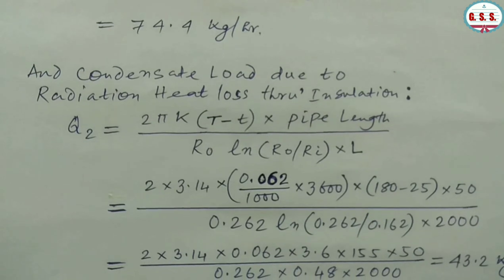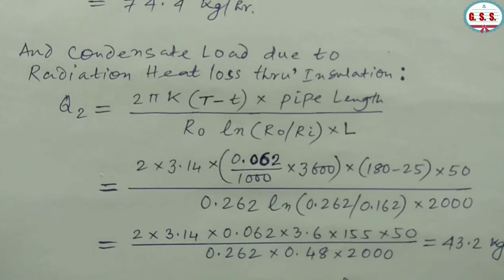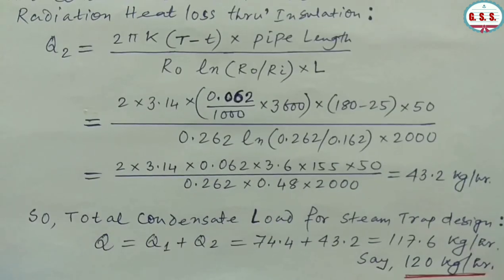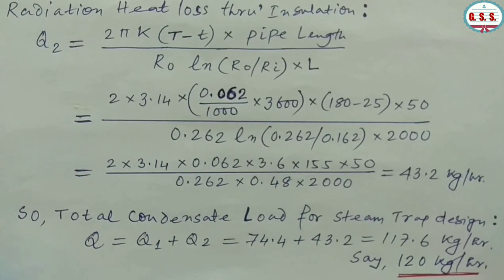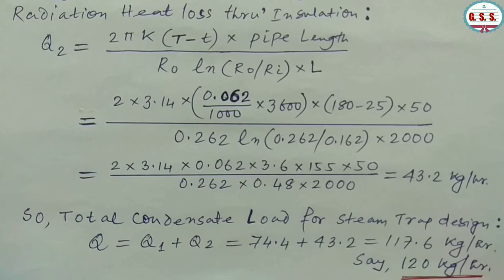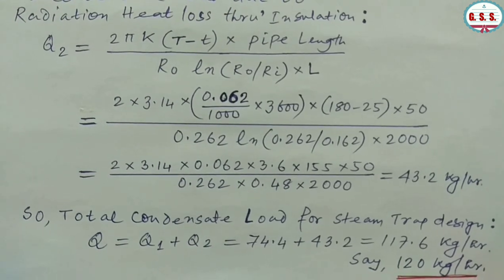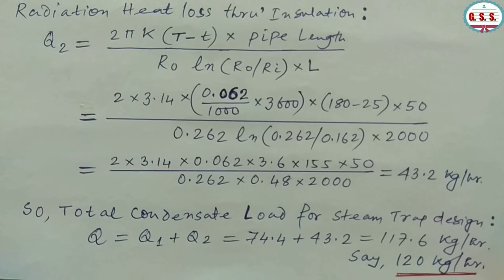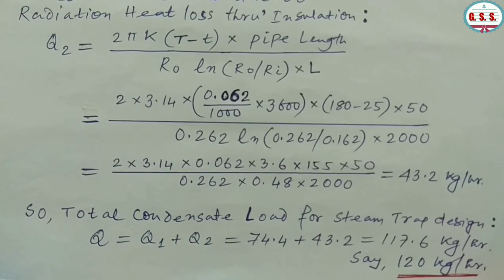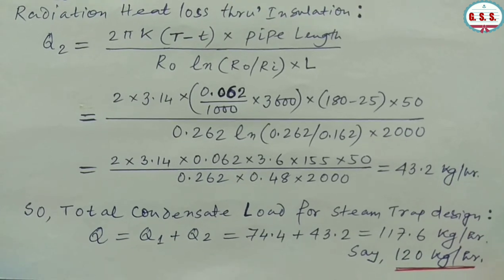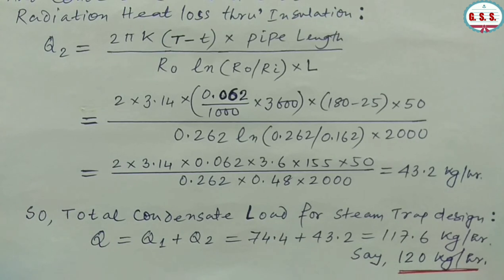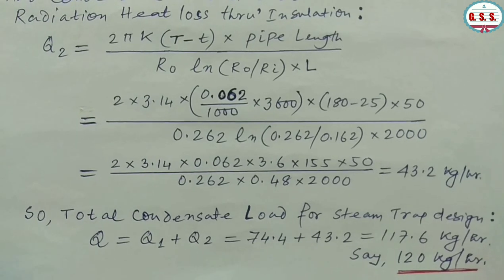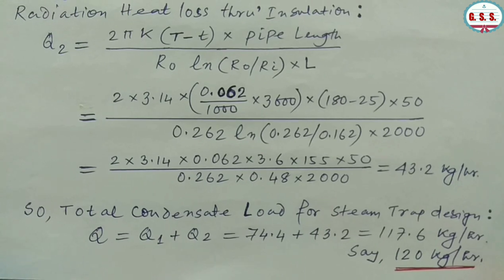Condensate load due to radiation heat loss through insulation: Q2 = 2π × K × (T − t) × pipe length / (R0 × ln(R0/Ri) × L) = (2 × 3.14 × (0.062/1000) × 3600 × (180 − 25) × 50) / (0.262 × ln(0.262/0.162) × 2000) = 43.2 kg/hr. So total condensate load for steam trap design = Q1 + Q2 = 74.4 + 43.2 = 117.6 kg/hr.